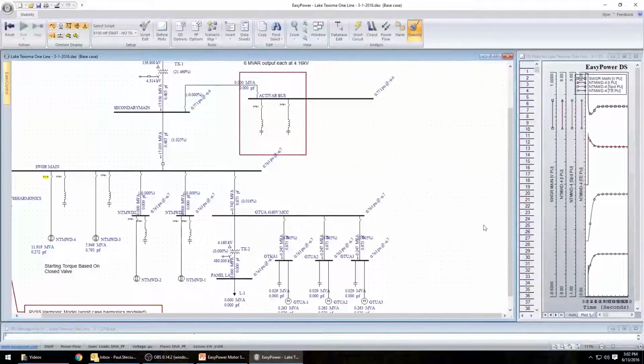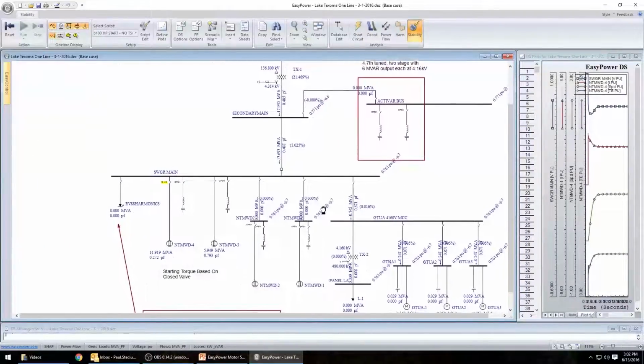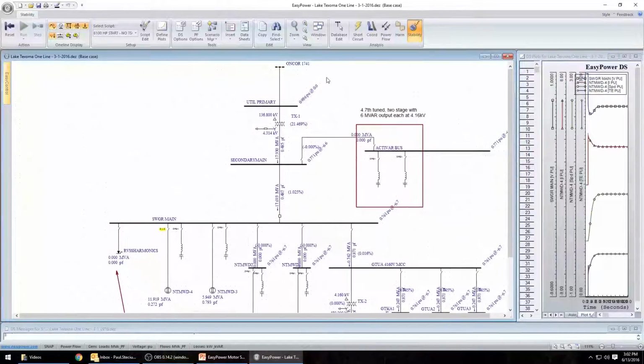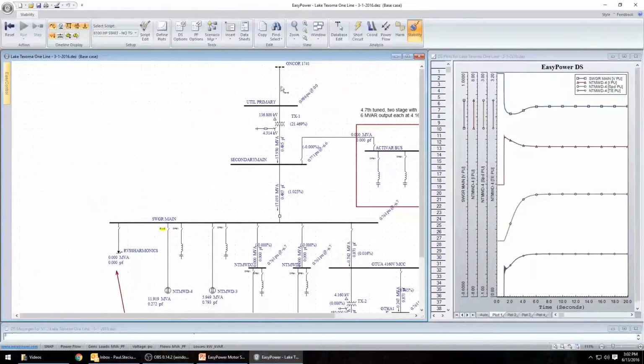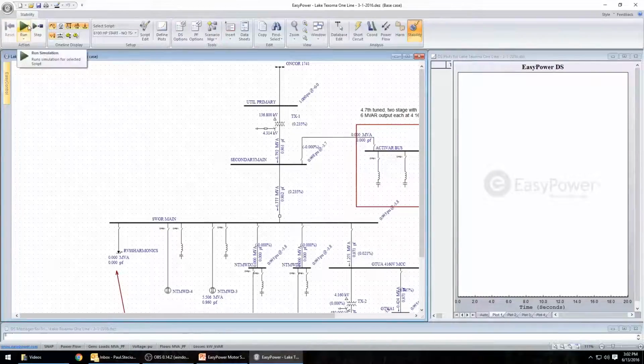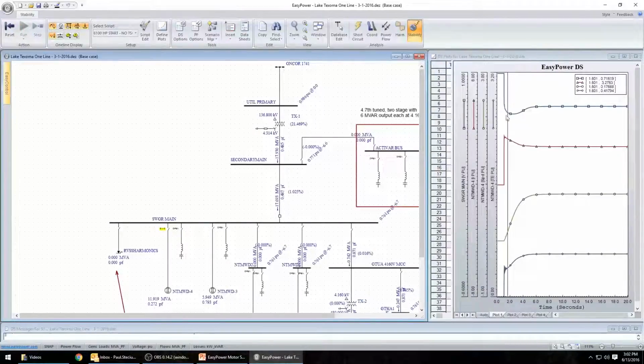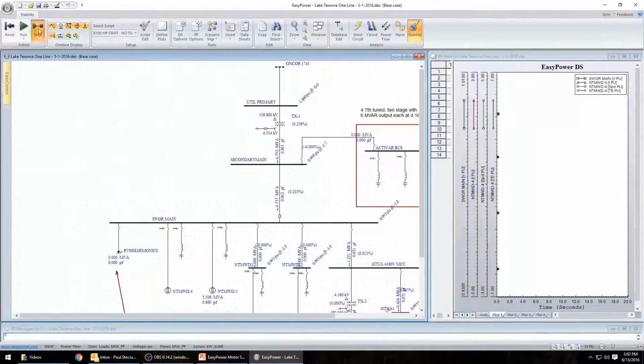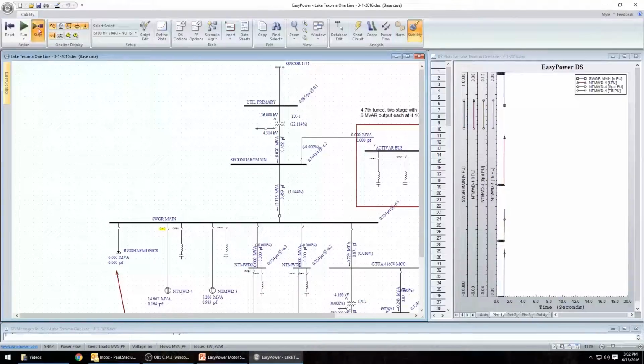Another interesting thing to do with the stability program, and I find it very useful in reports, is to step through the script step by step and watch what's going on. So I'm just going to hit a reset here, and instead of hitting run, where we get the full simulation, I want to step through, and at 1 second I click through. At 1 second you can see the power flow. So we're at roughly 18 MVA of power to help start this motor, at a 0.423 power factor.